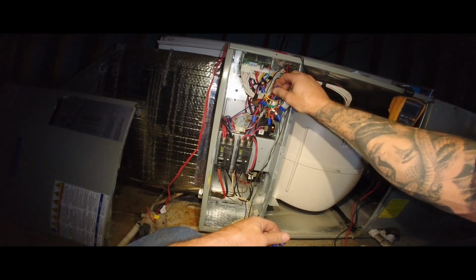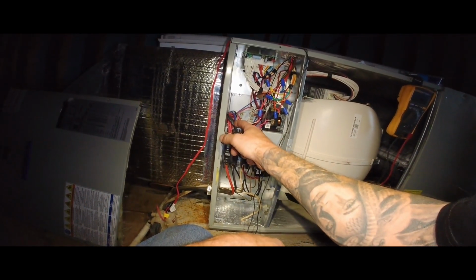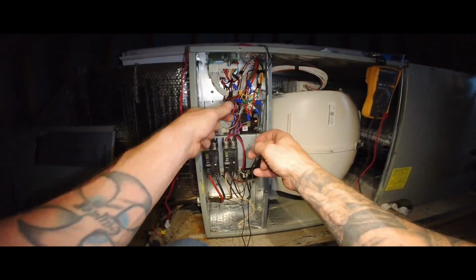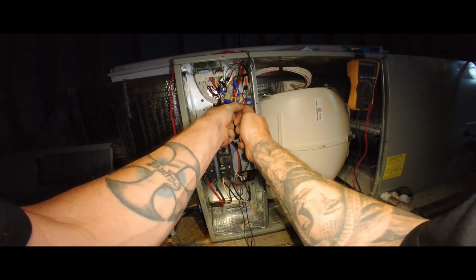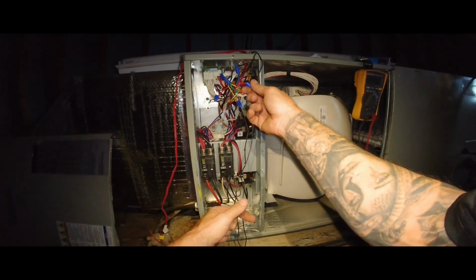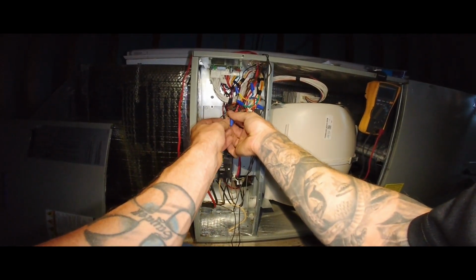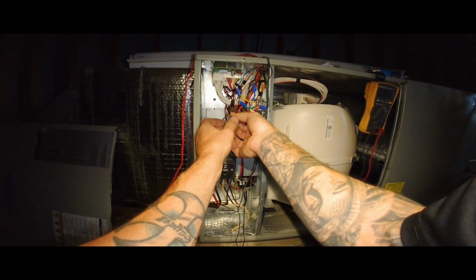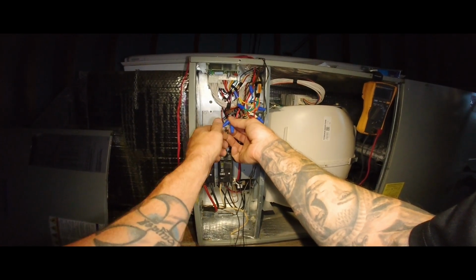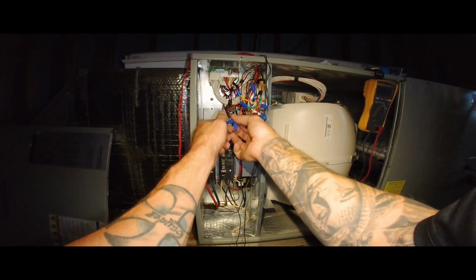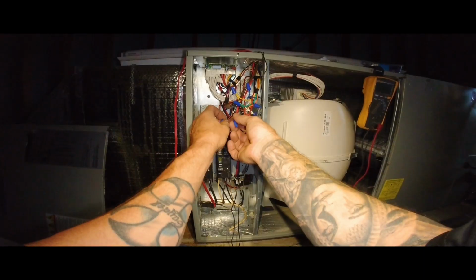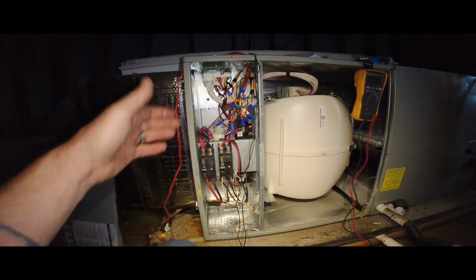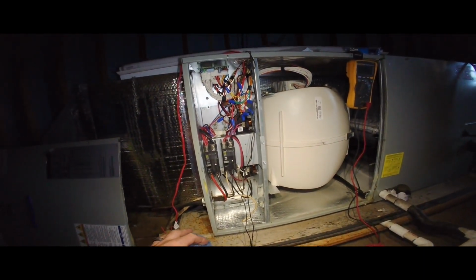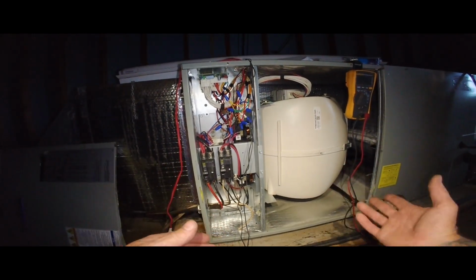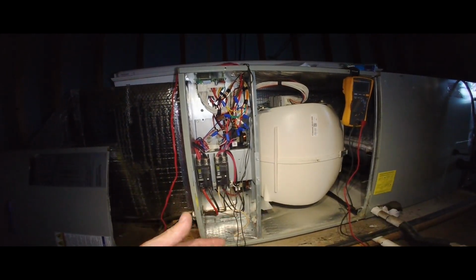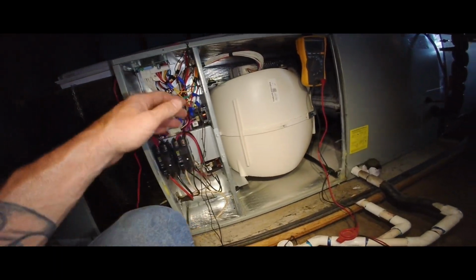Now what a transformer does is take 240 volts and transform it into 24 volts AC. The 24 volt signal, all these thermostat wires and stuff, isn't high voltage. You can touch it - as long as your hands aren't a little moist or sweaty, it won't get you like that. But that transformer supplies the thermostat with all these little signals, and the thermostat throws 24 volts down this wire, down that wire, to make the fan run, make the outdoor unit run, all that kind of stuff.